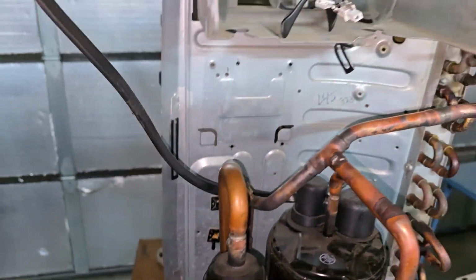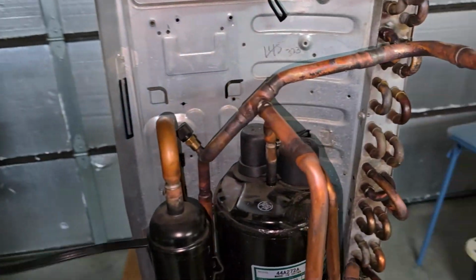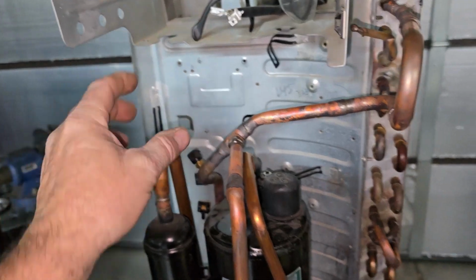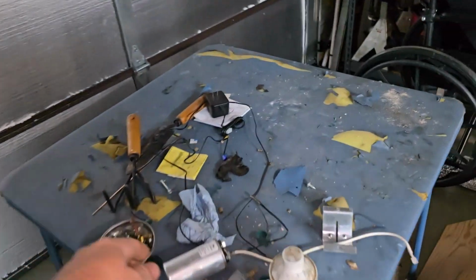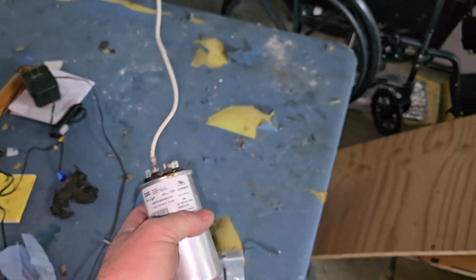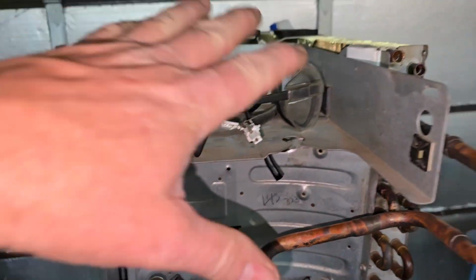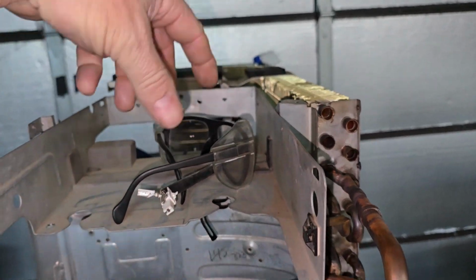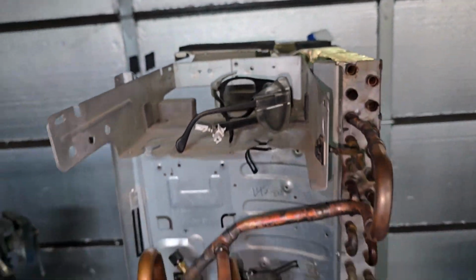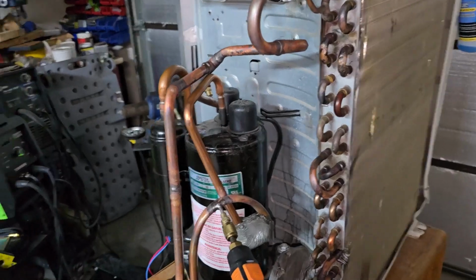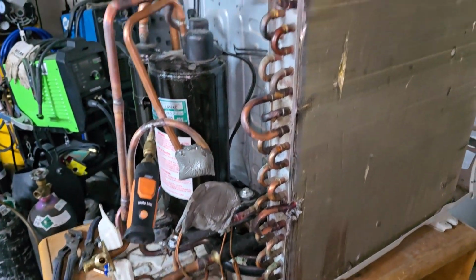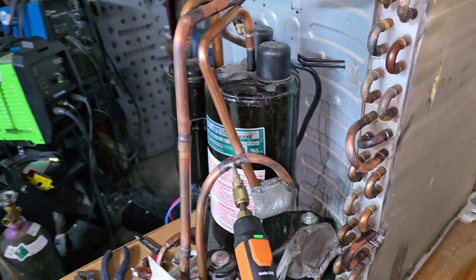This is a single phase 230 volt compressor, so I got that ready to go. I'll need to put the capacitor in there. This is the actual capacitor and bracket that came off the unit, I took it out of it. It was a running unit. So I got to mount that in there somewhere, and I'll probably put the IPM up here and then my little basic controls up there to stage the pump and all that stuff based on liquid line temperature.